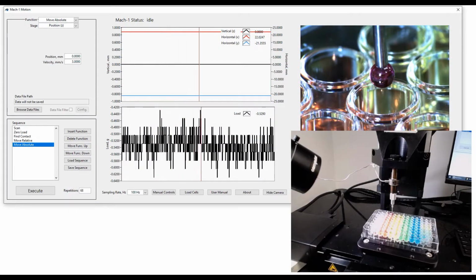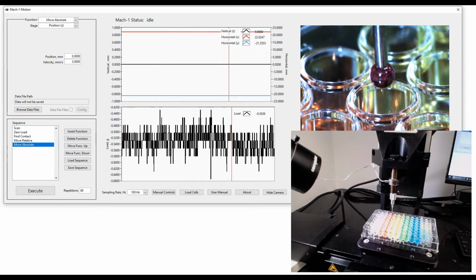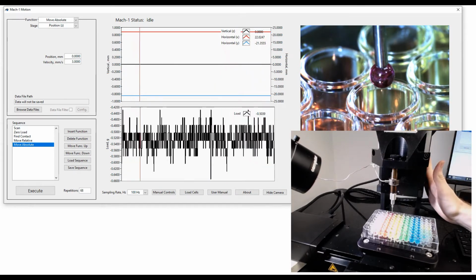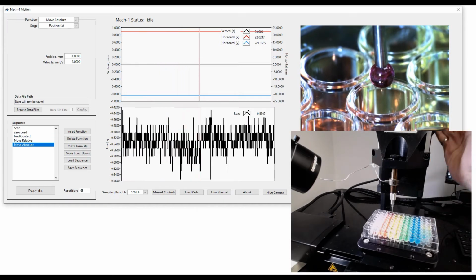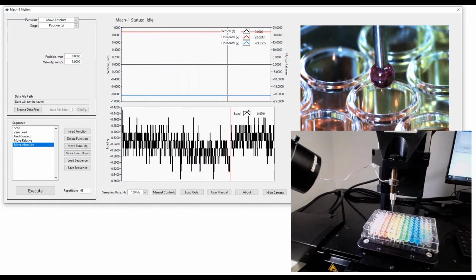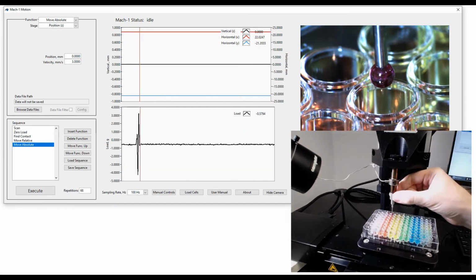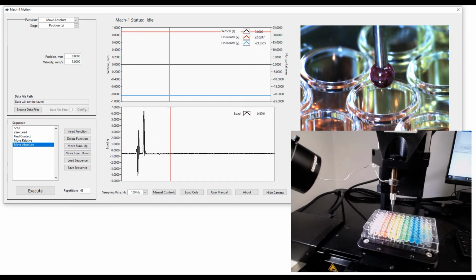Hi, I'm Nicholas, one of the mechanical designers here at Biomomentum, and what we have here today is a Mach-1 V500 CSS system, which means it has 3 actuators, one in the vertical direction and 2 in the horizontal direction, X and Y. We also have a 500-gram load cell, which you can see right here if I touch it, and a 3mm diameter ruby ball indenter.